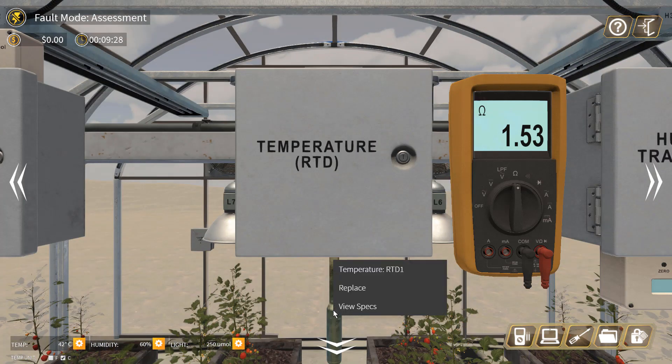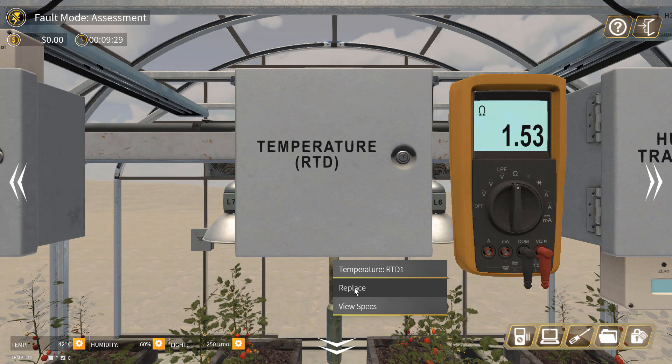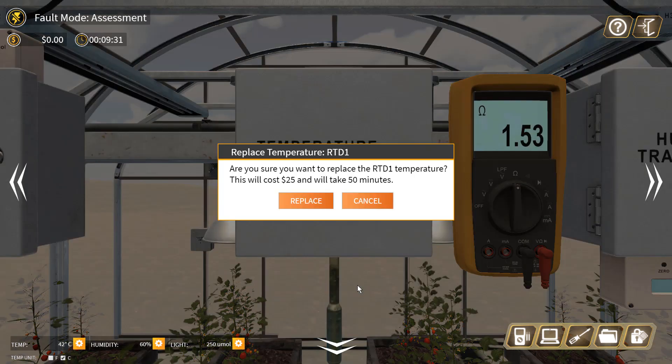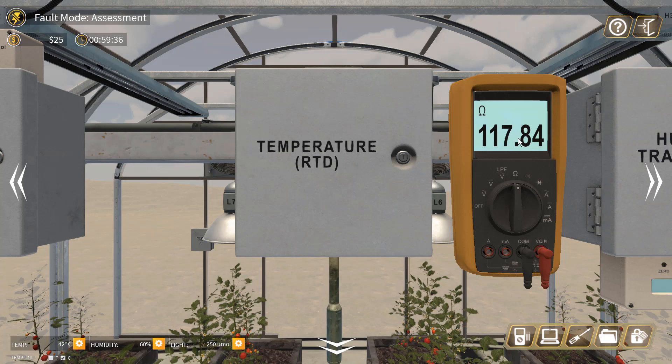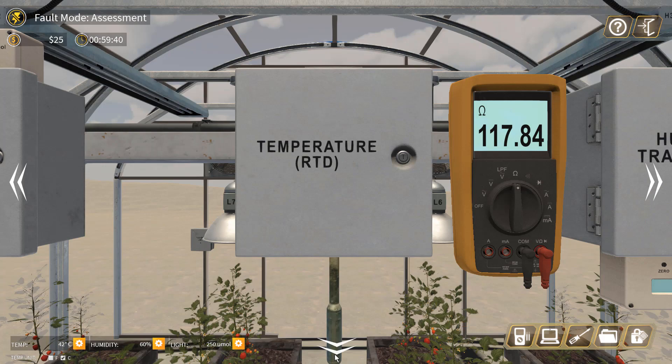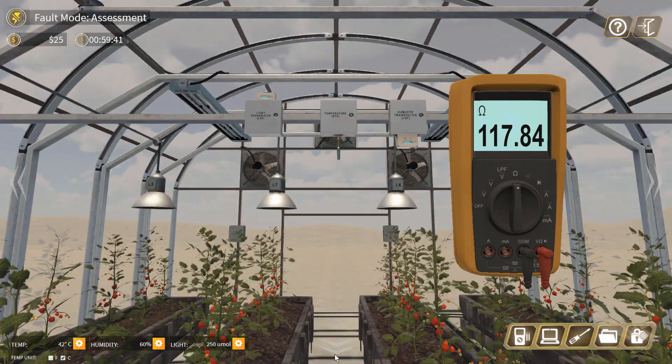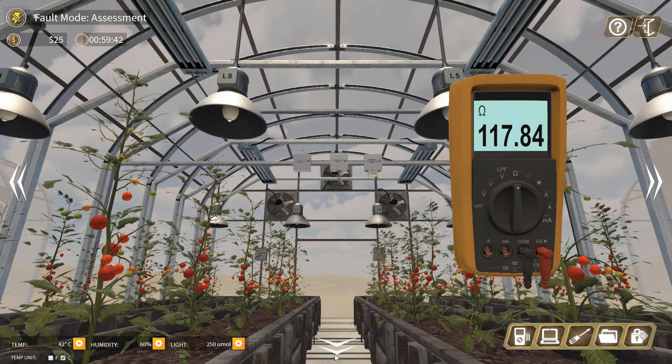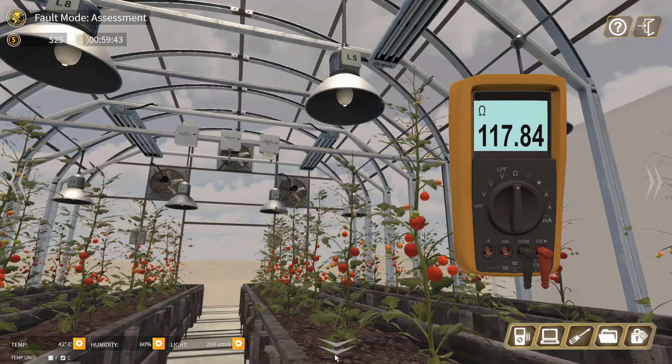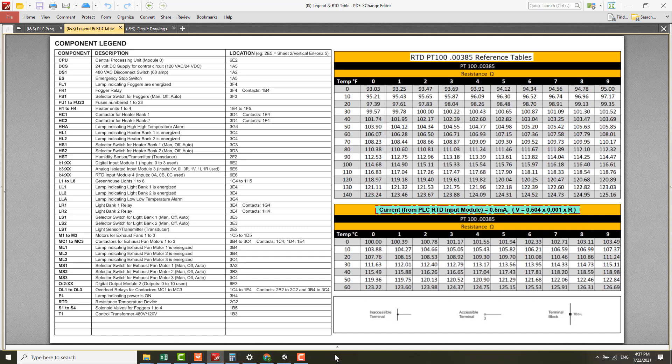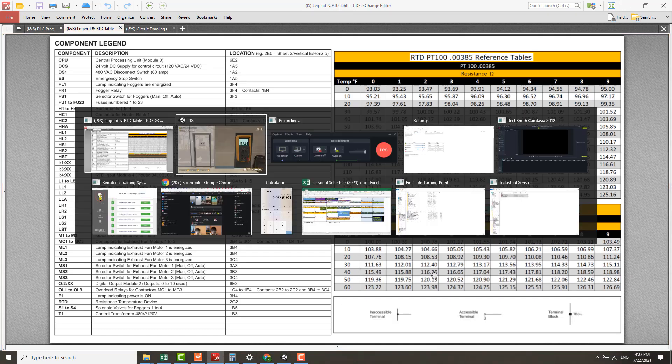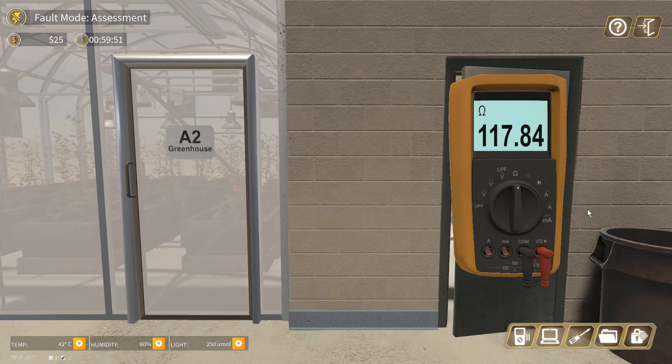We replaced the RTD here. All right, now the resistance it gives you is 117 ohms - this is correct. We can double confirm whether the resistance is the correct one or not. Now you know at 42 degrees it's about 116, right? Yes, about 116 is very close to that.